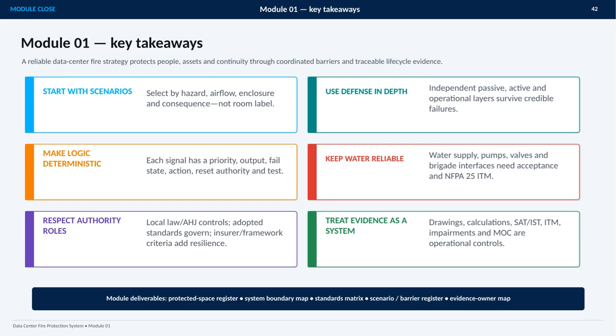Make the system logic deterministic as well. Every signal needs a defined priority, output, fail state, action, reset authority, and test method. Water reliability is equally essential. The supply, pumps, valves, and fire brigade interfaces must be accepted, maintained, and inspected through the appropriate NFPA 25 inspection, testing, and maintenance process. Authority roles also matter.